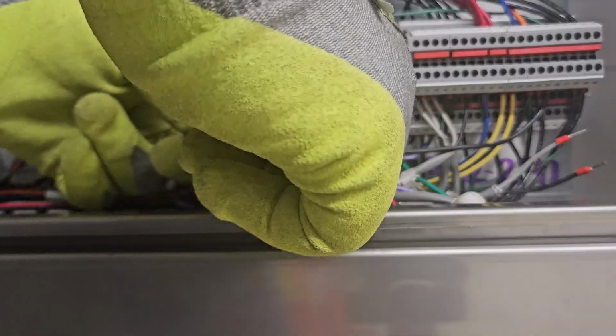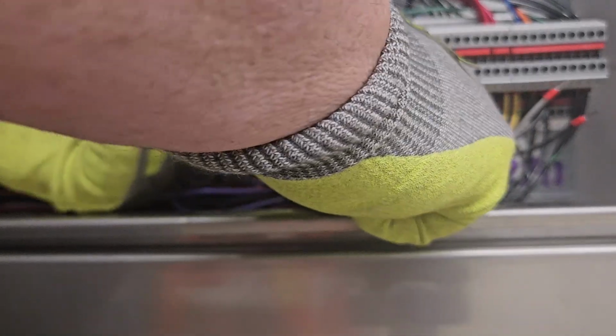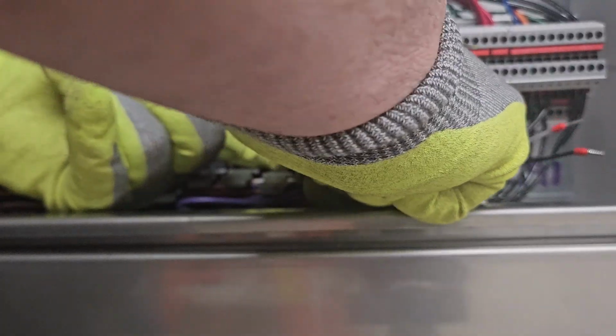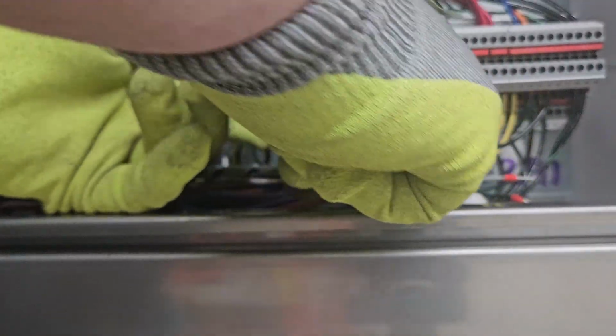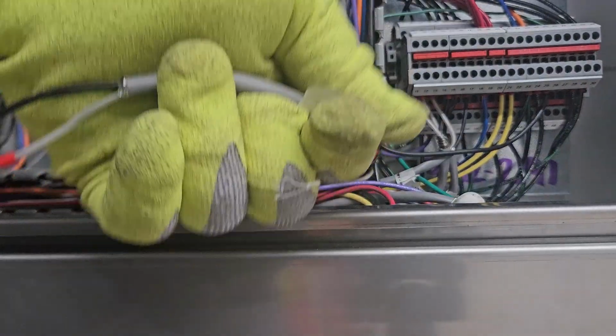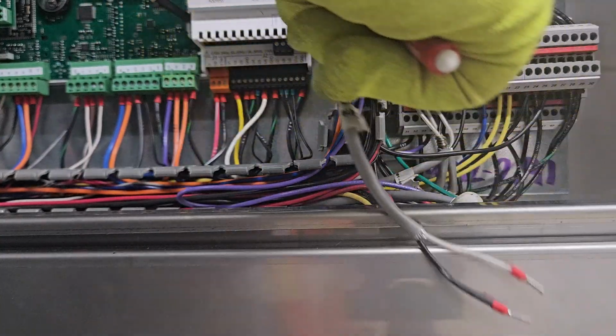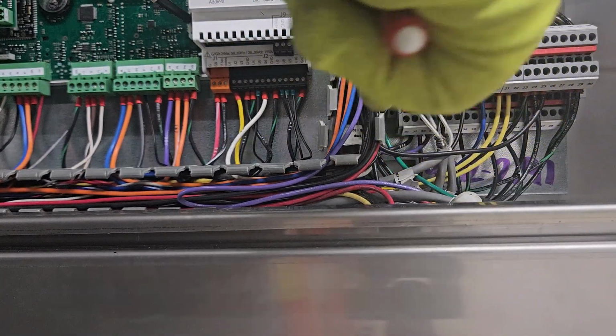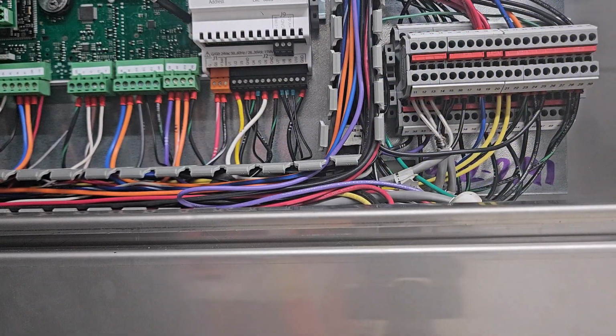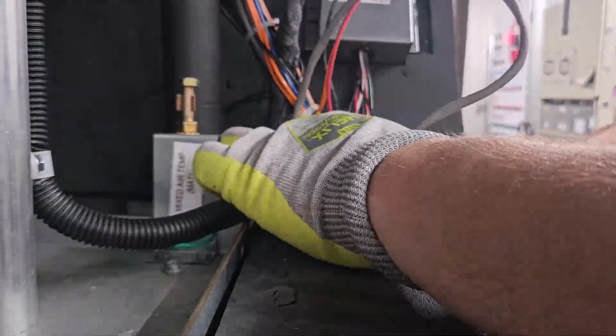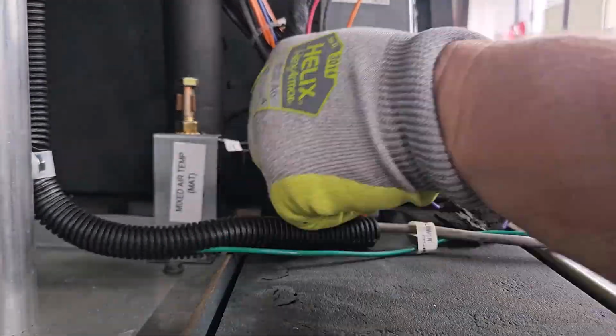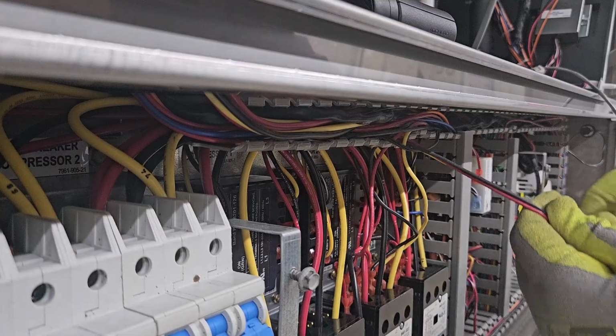Fish the wire out of the wire channel and be careful not to pull any other wires out of their location. This is easier said than done. If we are not careful at this moment, we could accidentally pull a wire out of the PLC control board. Remove the sealant material and pull the communication and grounding wire through the knockouts.